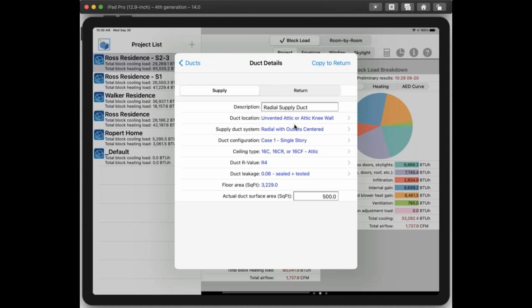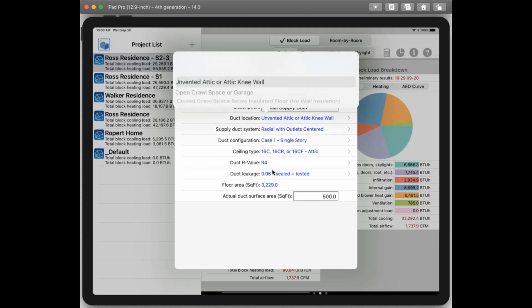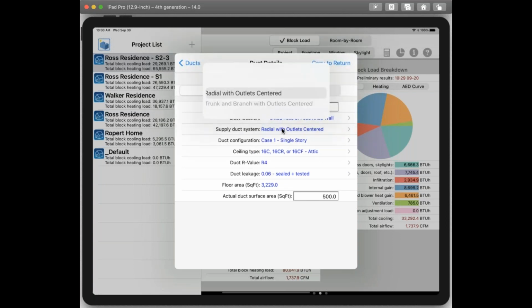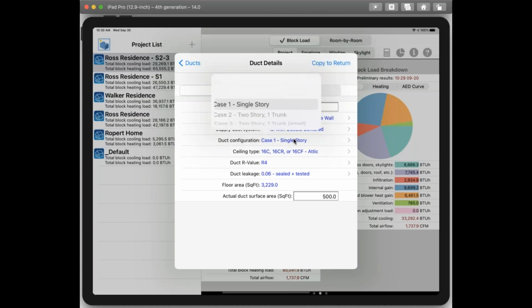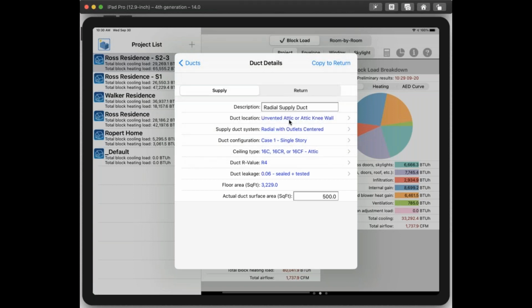So here we have our supply, and here's a bunch of parameters for our supply duct. I'll go through some of these quickly. Duct location, where is it located? What type of duct system? Radial, trunk and branch. What's the configuration? Single, 2-story. The ceiling type. In this case, because the duct is located above the attic, I want to know the ceiling type. These number letter combinations are actually ceiling types from the ACCA Manual J8 handbook, which I can show you under the envelope section in a bit.